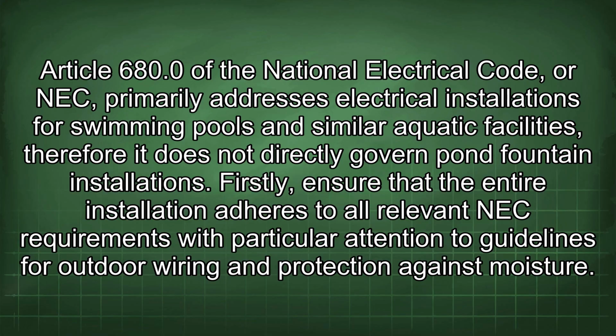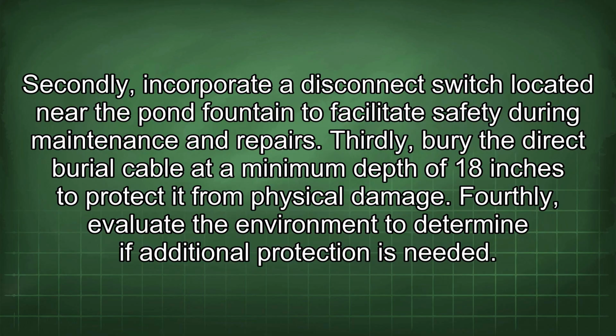Firstly, ensure that the entire installation adheres to all relevant NEC requirements, with particular attention to guidelines for outdoor wiring and protection against moisture. Secondly, incorporate a disconnect switch located near the pond fountain to facilitate safety during maintenance and repairs. Thirdly, bury the direct burial cable at a minimum depth of 18 inches to protect it from physical damage.